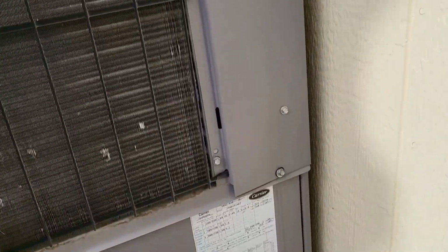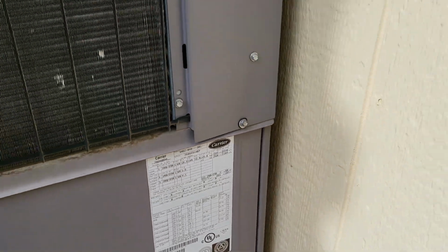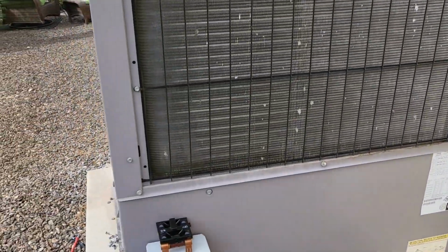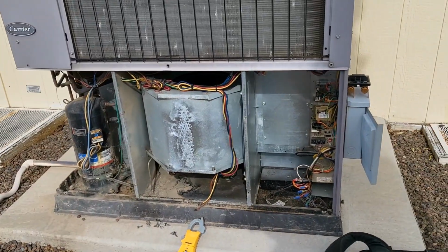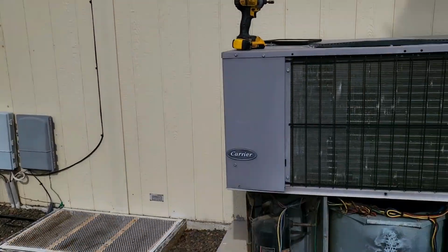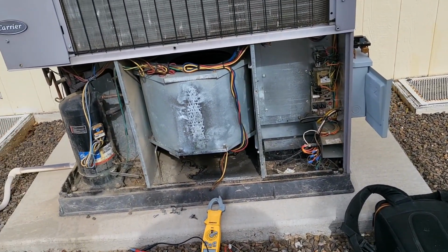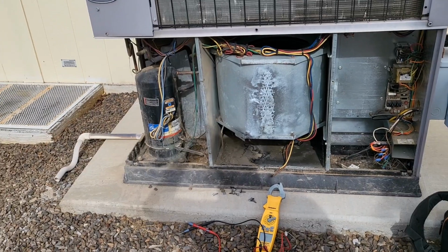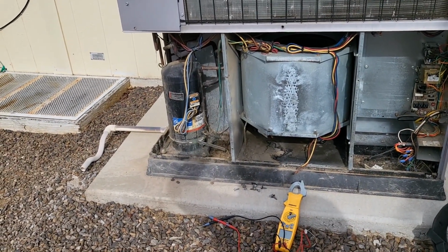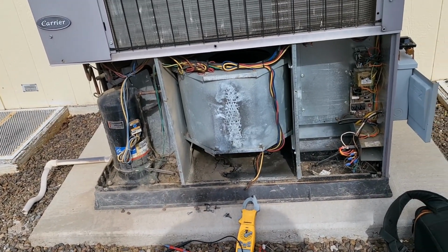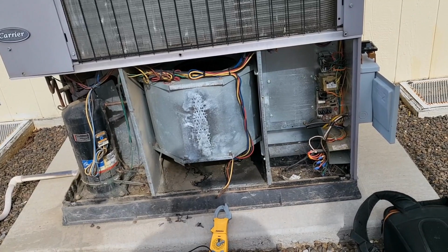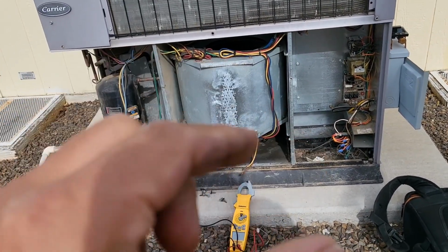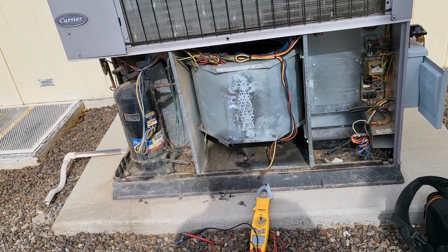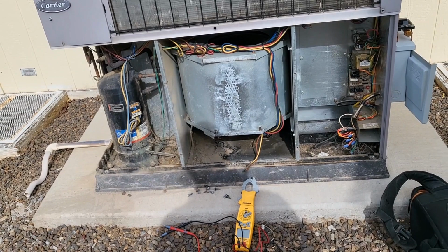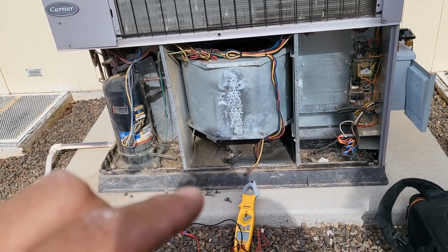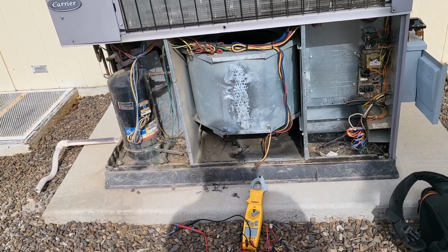Not to mention as well, this is not a high static unit, and it should be, because this is a manufactured or mobile home. It should have a system that can handle high static, because if we go inside, which we're not going to, you'd find that the vents where all the air comes out are all very slim ductwork. They're not bigger cans like we're accustomed to with bigger openings, they're always really slim with very thin duct. So you have to have a high static unit.